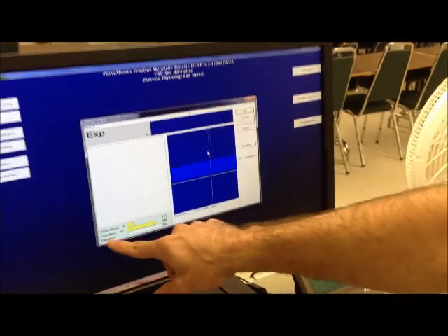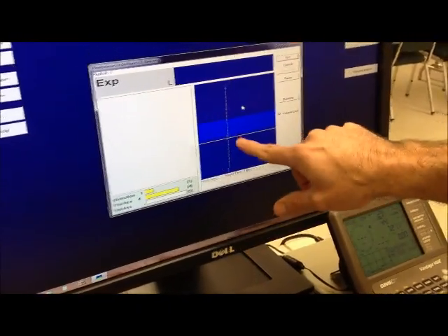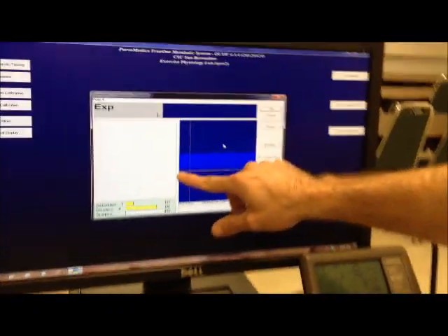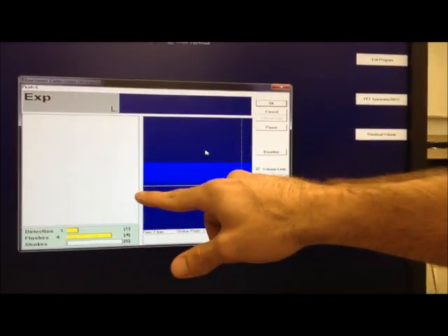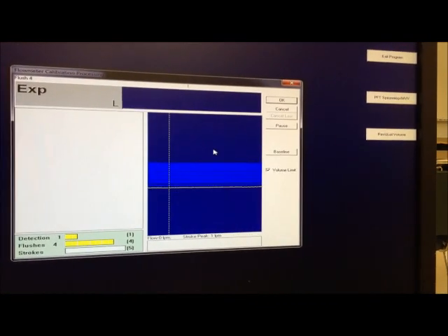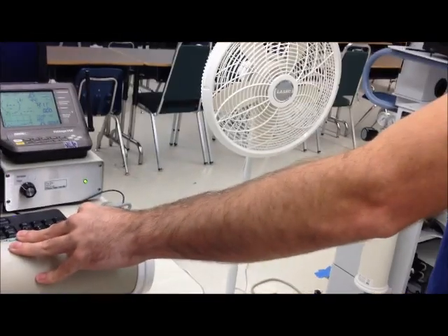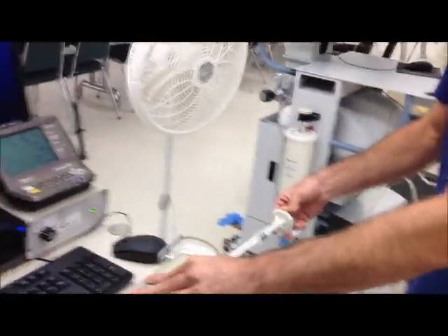For the next 5, it's actually looking for strokes. If you look right here, you see this yellow line. For the very first stroke, we want to just get it barely above the 0 line, so that's going to be a slow stroke speed, so you can focus on this. Between 50 and 100 liters per minute.